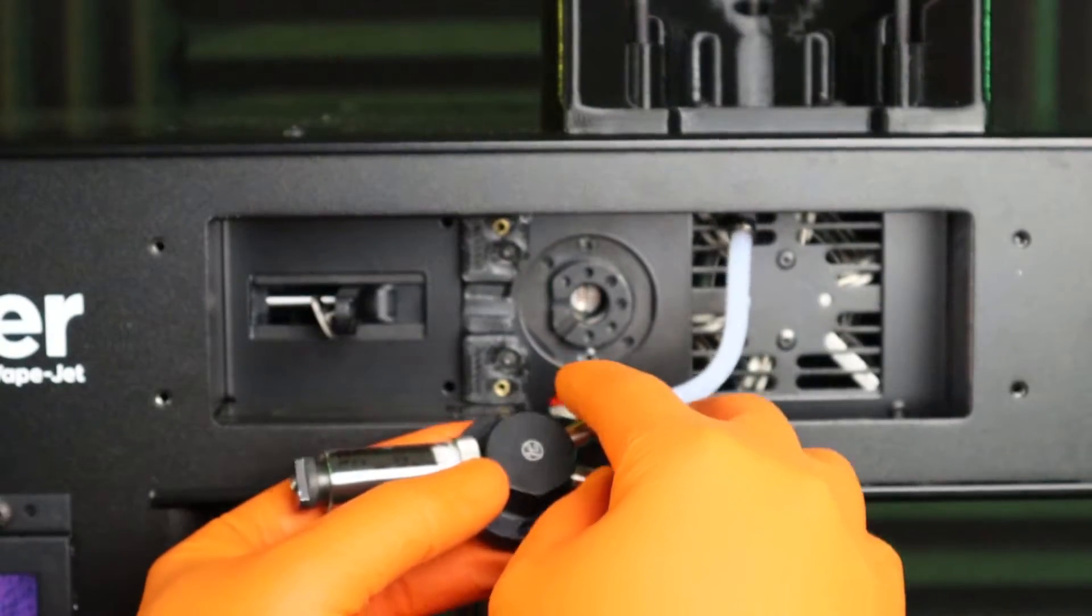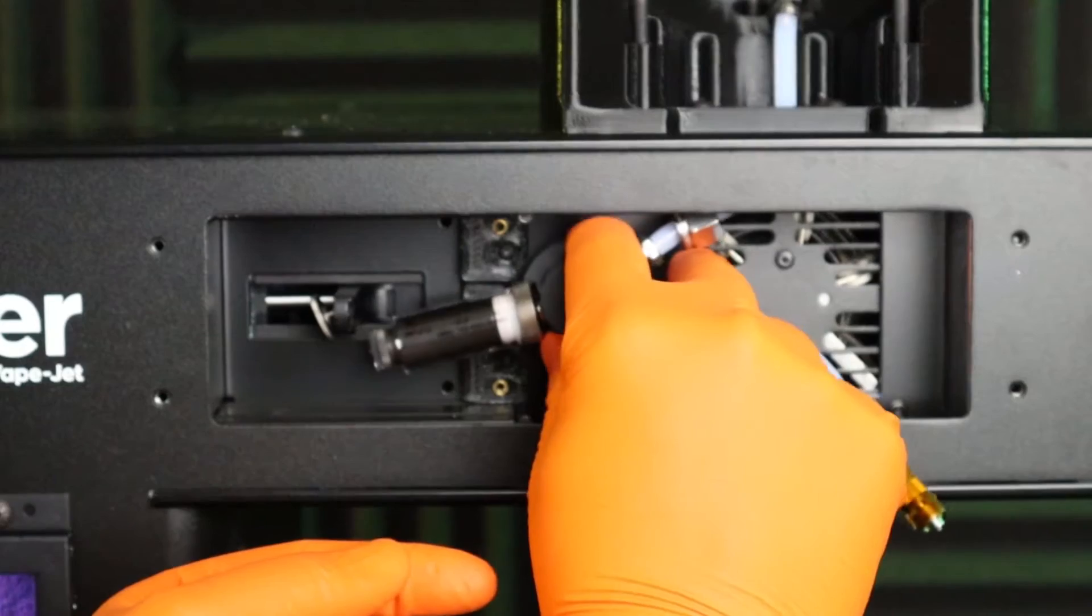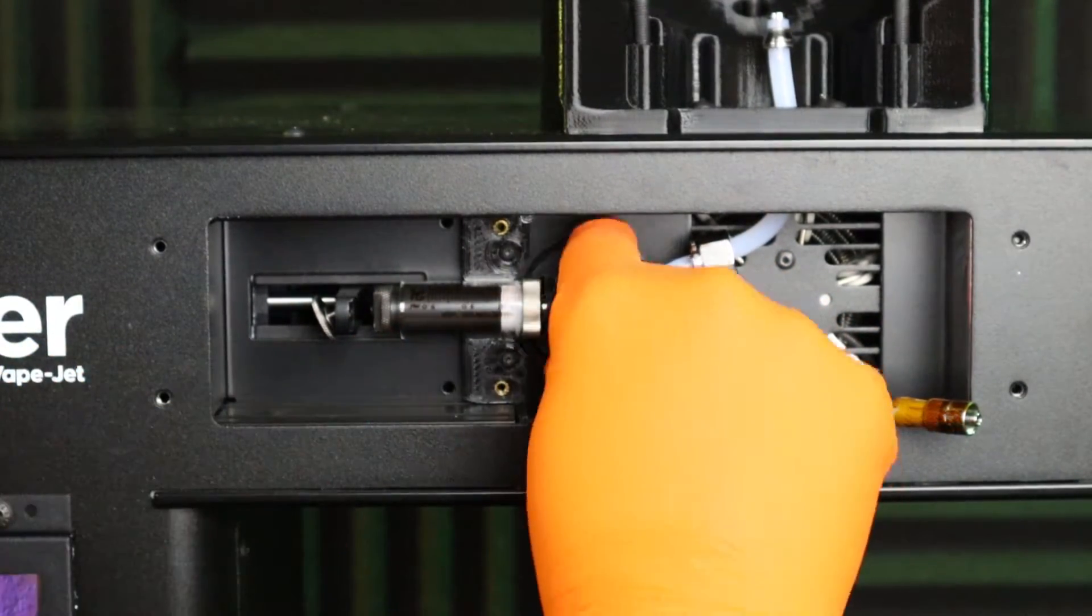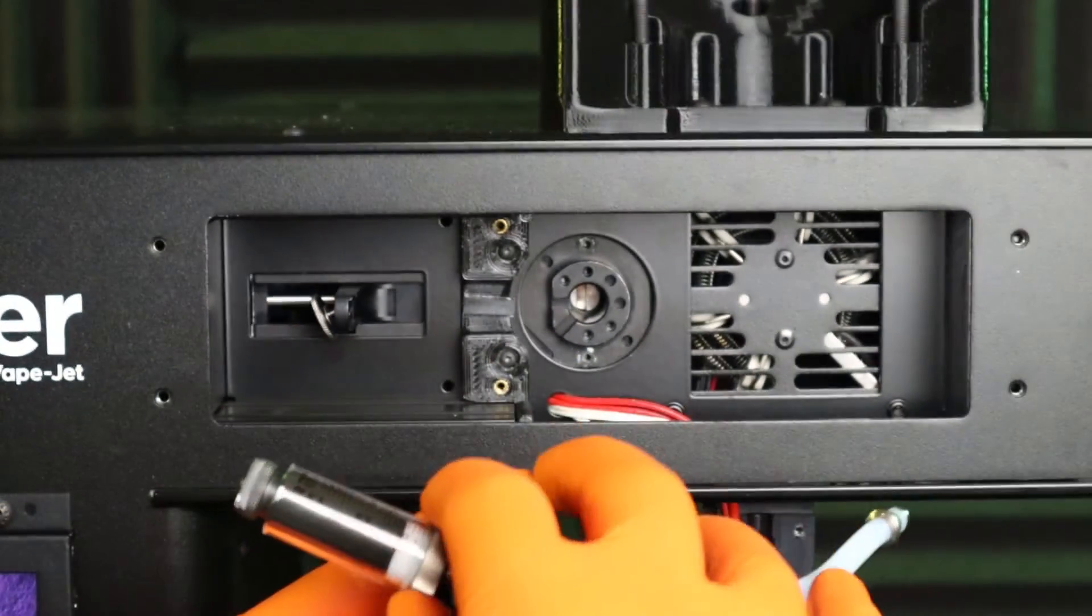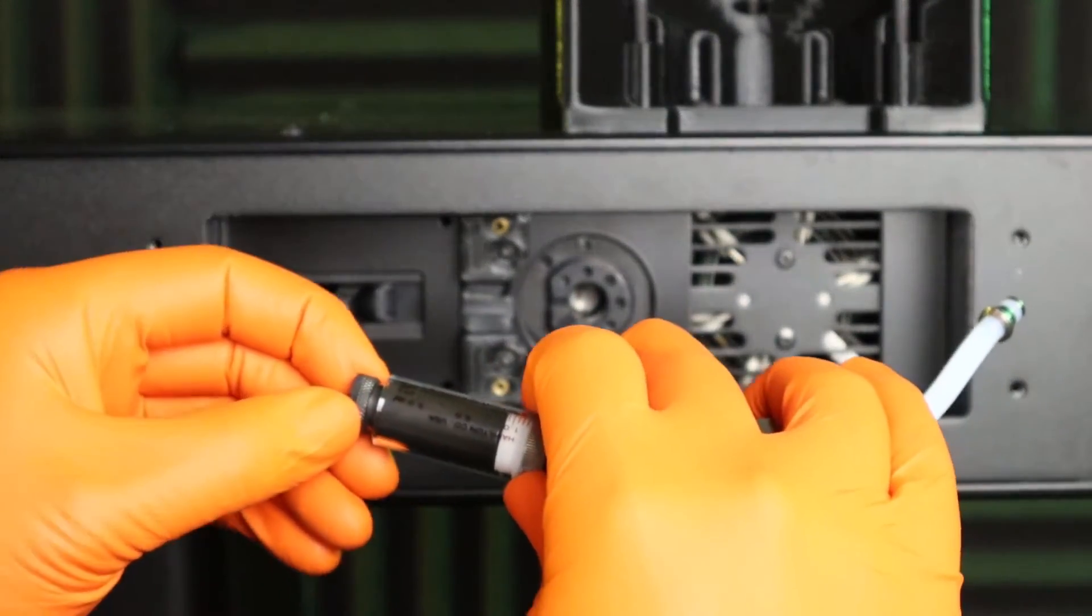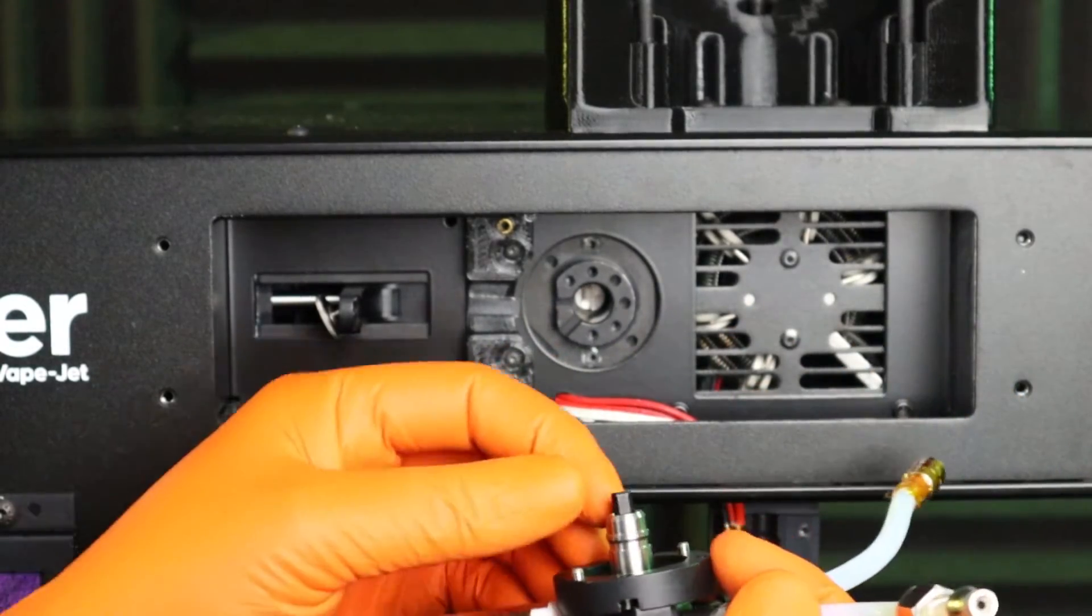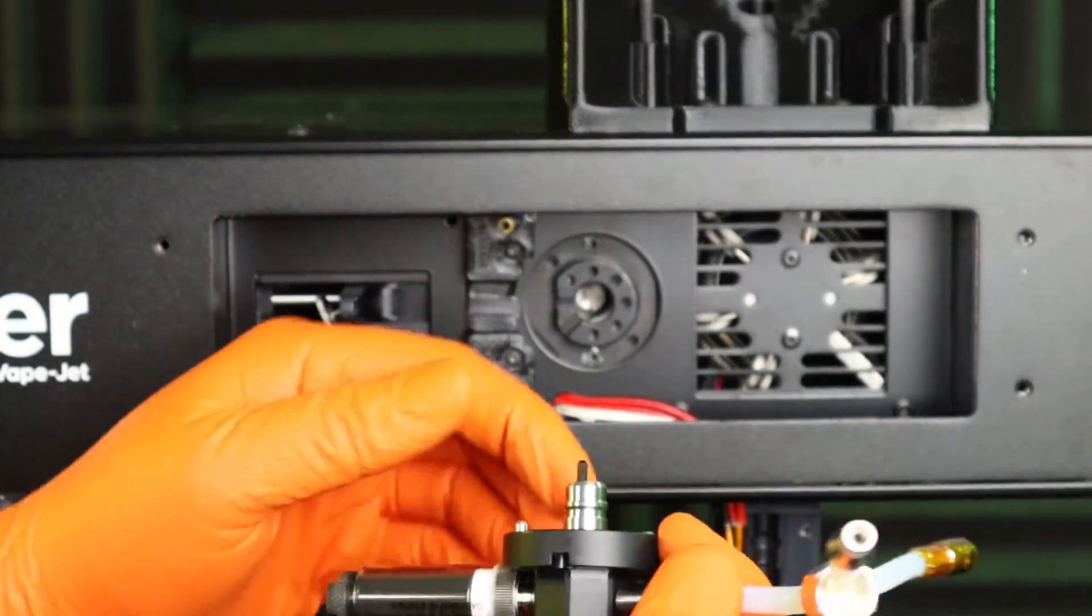Reinsertion of the syringe and valve assembly must be done gently in order to avoid damaging the syringe glass. Reconnecting the syringe plunger to the pump translation stage will require the syringe key to be aligned to the translation stage so that it may slide in. Ensure the key is aligned prior to seating the syringe valve assembly by gripping the syringe glass and plunger. Do not attempt to align the plunger key after the valve assembly is installed. The port selector on the rear of the valve must be aligned to the slot inside the valve mount.